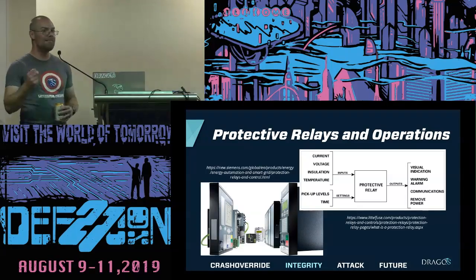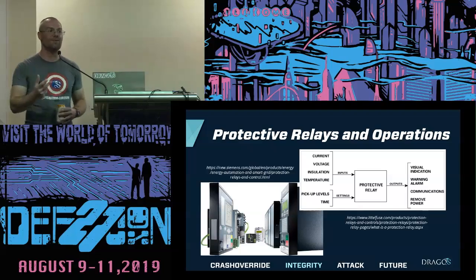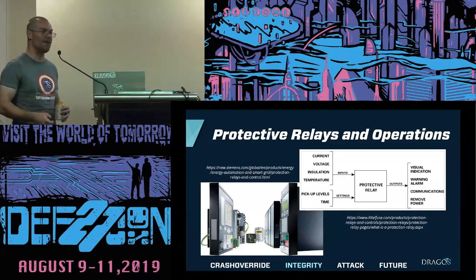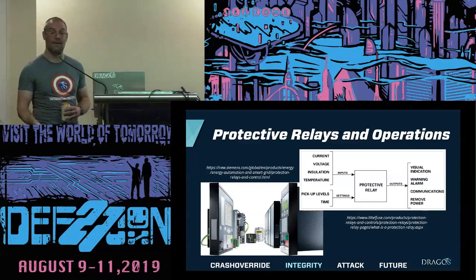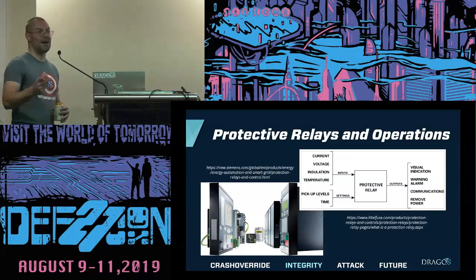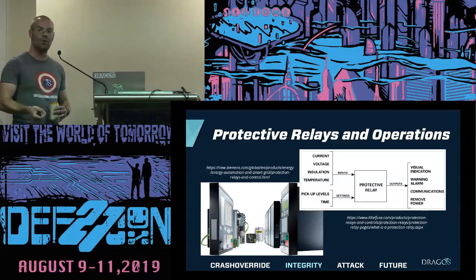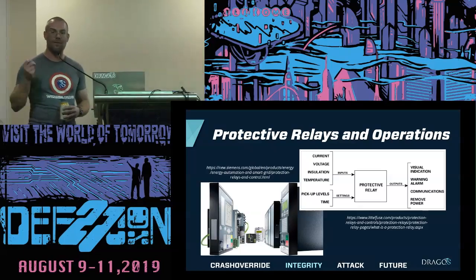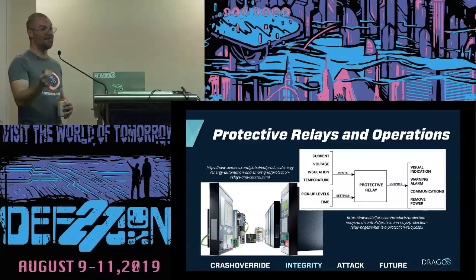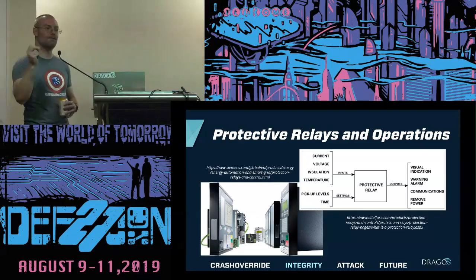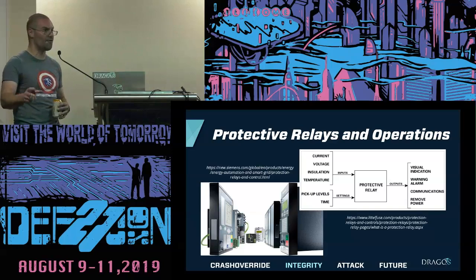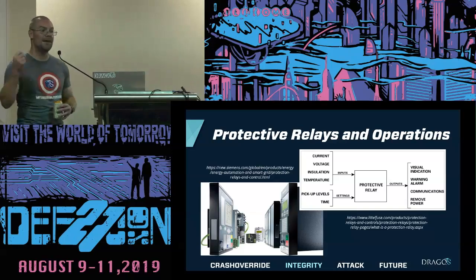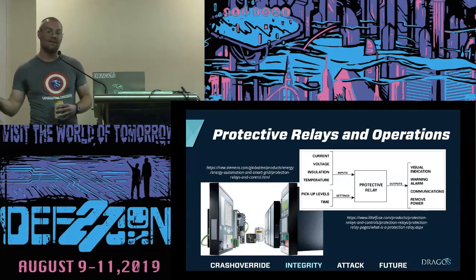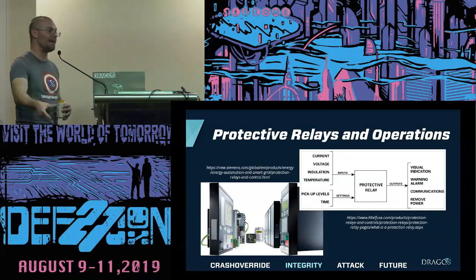One of the major revolutions in electric operations over the last 20, 30 years is the introduction of digital protective relays, which are able to autonomously and at machine speeds monitor and control electric transmission operations to prevent things like a fault in the electric line due to overcurrent, phase out of whack, or other scenarios resulting in physical damage or potential cascading outages from propagating defects within the grid environment.